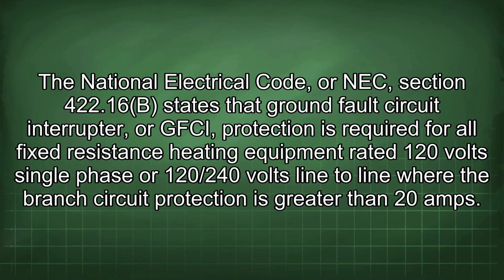National Electrical Code, or NEC, Section 422.16(b) states that ground fault circuit interrupter, or GFCI, protection is required for all fixed resistance heating equipment rated 120 volt single phase or 120/240 volts line to line where the branch circuit protection is greater than 20 amps.